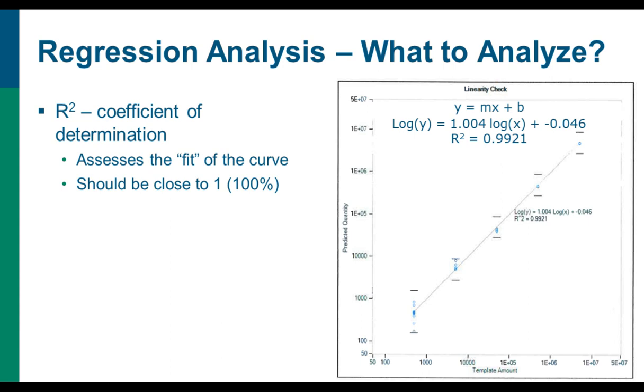So in regards to what to analyze, there are a few different things you want to look at, and this is one of our curves here. This is actually a really beautiful curve. They don't always look this nice, but it is a nice example. If you remember, I don't remember if it was grade school or middle school, but we learned about y equals mx plus b, which is the equation for a line, where m equals your slope and b equals your bias. And then r squared is another point that will be analyzed. This is your coefficient of determination, which will assess the fit of the curve. Your r squared should be as close to 1 as possible, or 100%. If you can see at the top of the graph on the right, the r squared is 0.99, so 99%. That's a very good fit.